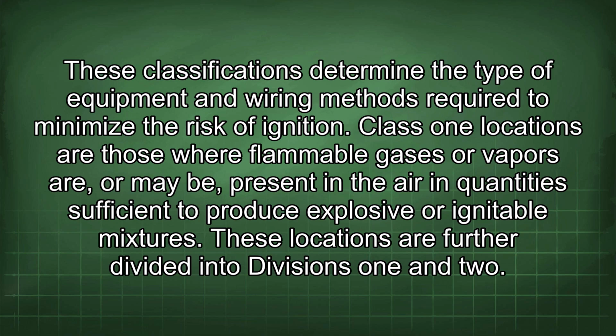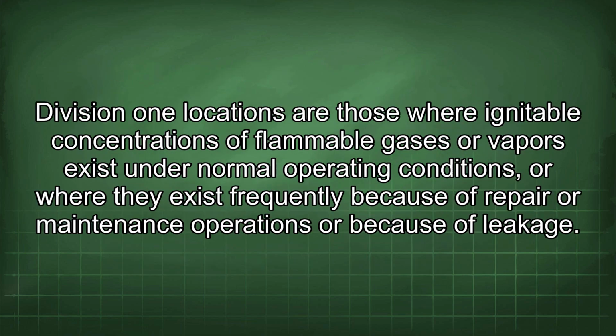Class 1 locations are those where flammable gases or vapors are, or may be, present in the air in quantities sufficient to produce explosive or ignitable mixtures. These locations are further divided into Divisions 1 and 2. Division 1 locations are those where ignitable concentrations of flammable gases or vapors exist under normal operating conditions, or where they exist frequently because of repair or maintenance operations or because of leakage.